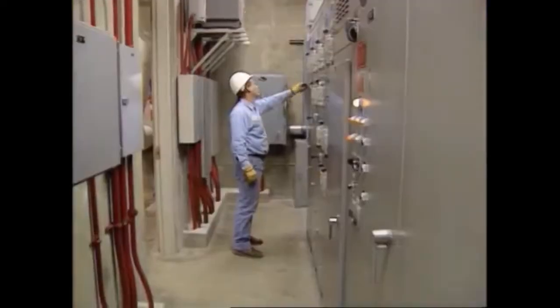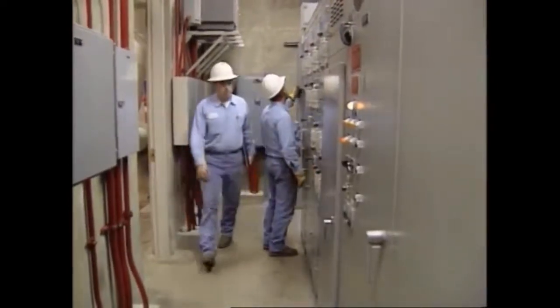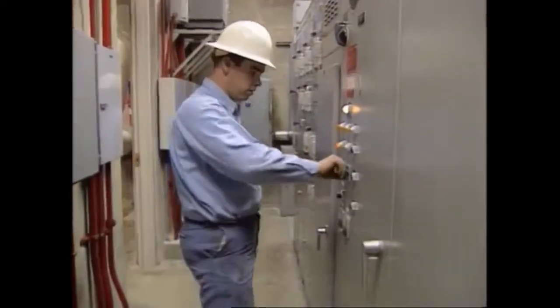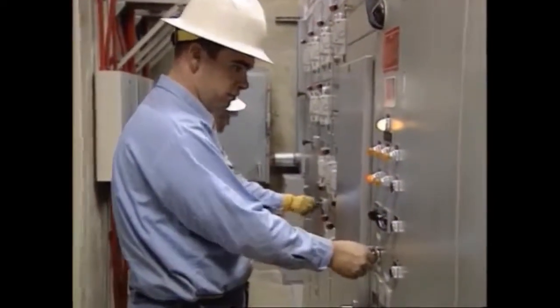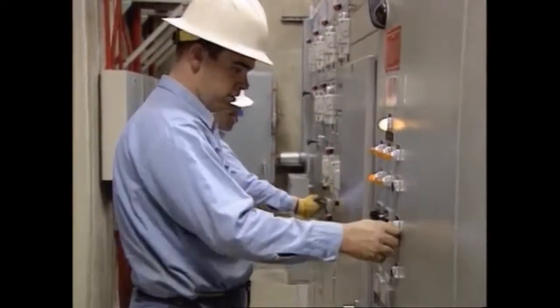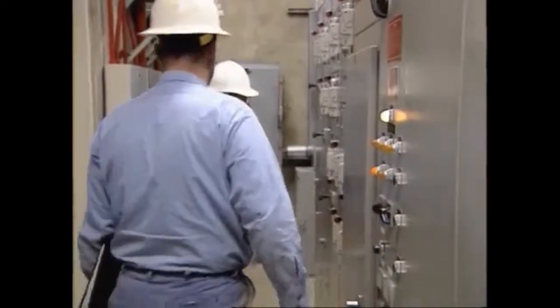Next in the station alarm inspection procedure is inspection of the control panel and the power center. If the dry well area is not flooded and equipment looks normal, in other words, there are no broken pump shafts, no pump shafts rotating backwards, and the valves are closed and seated, then return to the motor control center and power panel. In some stations, full power can be restored to all operating equipment at one time. In other cases, especially where large pumps are used, full power should be restored one unit at a time. In any case, follow the standard operating procedure for that particular station.